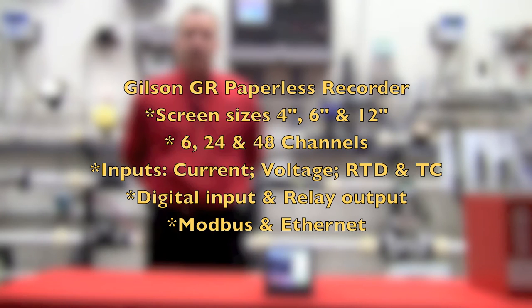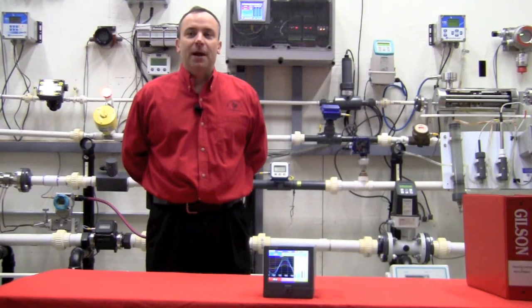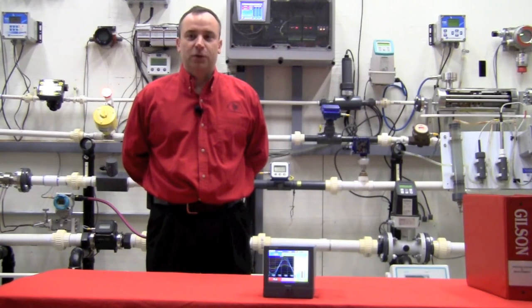The unit also has digital inputs and relay outputs when equipped. Additional features include Modbus TCP IP over Ethernet and removable data storage via USB and SD cards. The recorder can be powered via 90 to 250 VAC or 11 to 36 VDC.